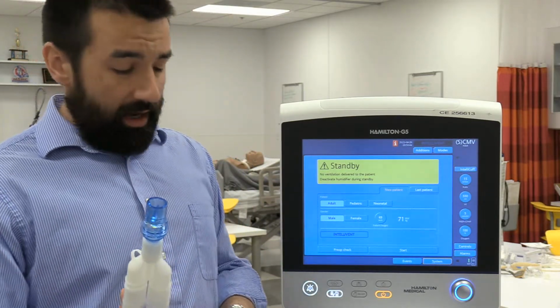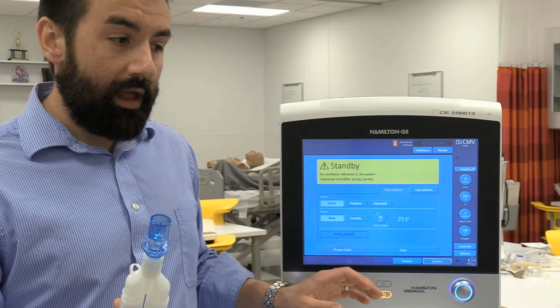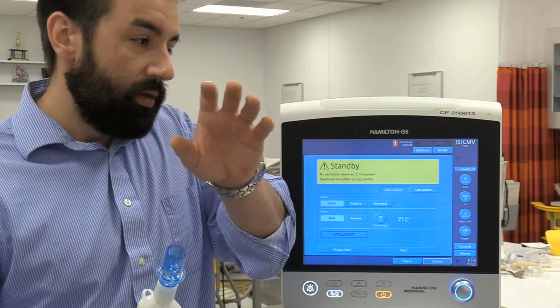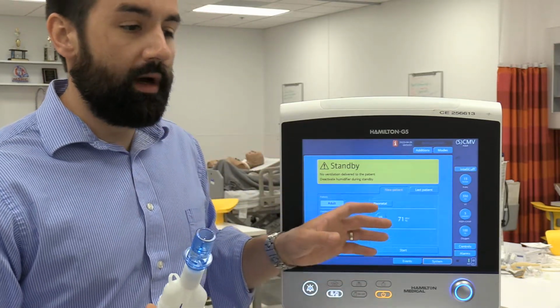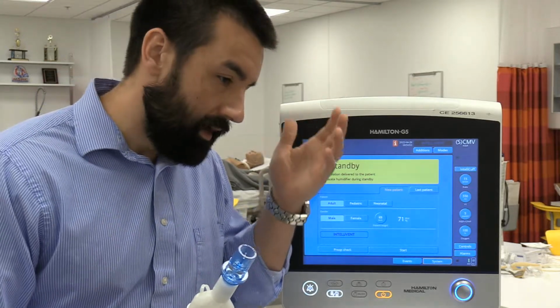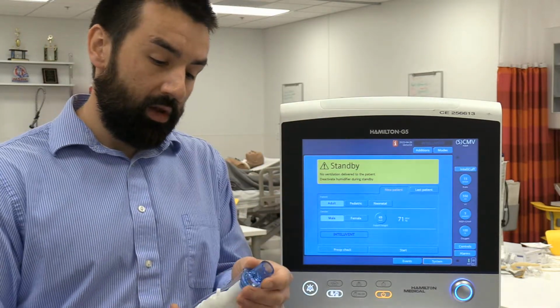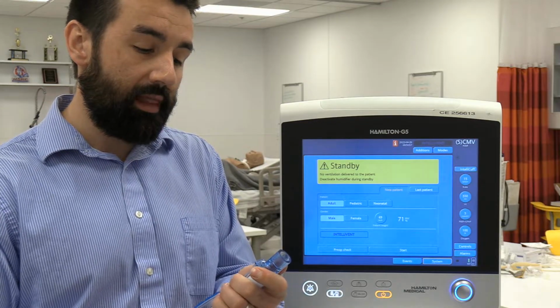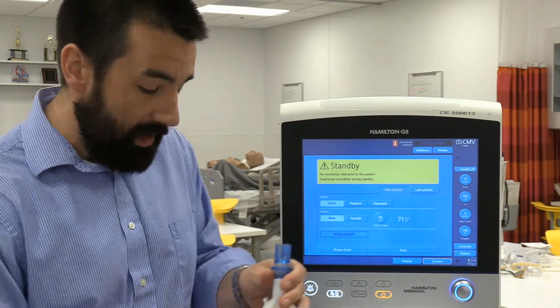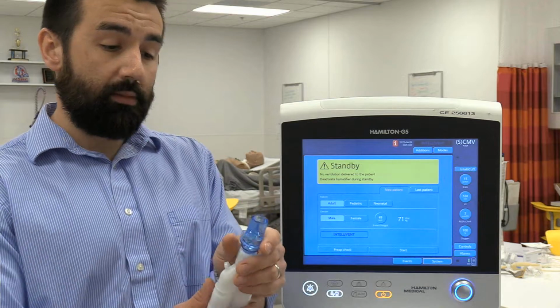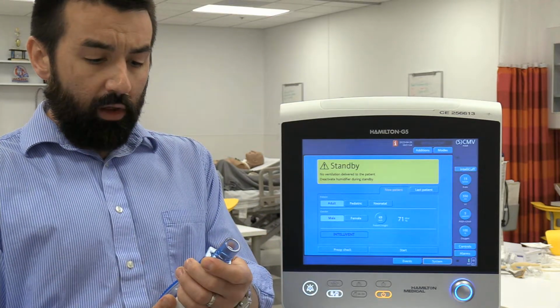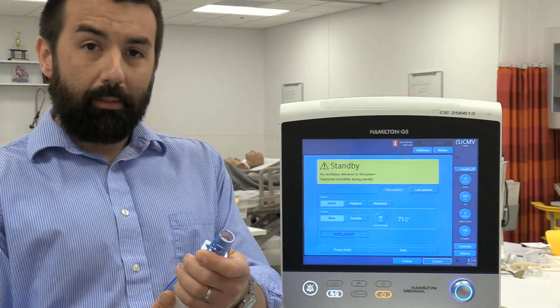Most ventilators have the flow sensor on the expiratory side of the ventilator, so all the gas has to go through the Y all the way back to the vent before any of the measured flows are turned into volumes, and all of our readout on the ventilator is displayed. Likewise, the same thing takes place with triggering. It's all happening back at the expiratory side on most ventilators. And if something goes wrong with the flow sensor, we don't really have the ability to fix that. That's a biomed kind of thing.